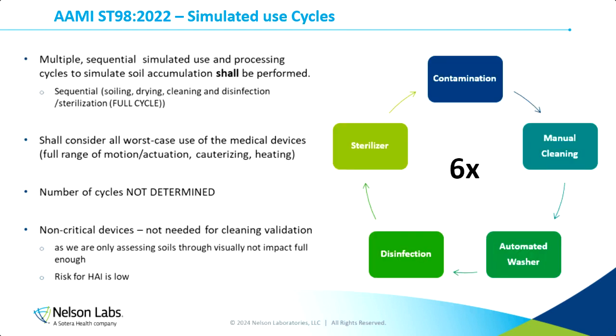To start off with simulated use cycles. As I mentioned, these are multiple sequential cycles of the entire reprocessing cycle. We contaminate the device, take it through the cleaning process, and then disinfect or sterilize based on the classification of the device and the IFU. In AAMI ST98, these simulated use cycles shall be performed for semi-critical and critical devices. During these cycles, we need to consider all of the worst-case use of the device. We need to consider the full range of motion of the device, and actuate the device during soiling. If it involves cauterizing tissue, we need to consider doing that during these cycles.